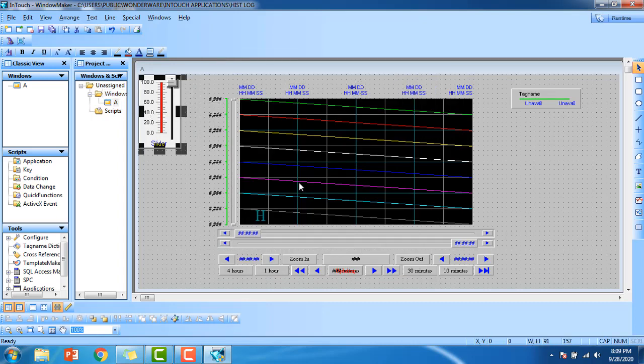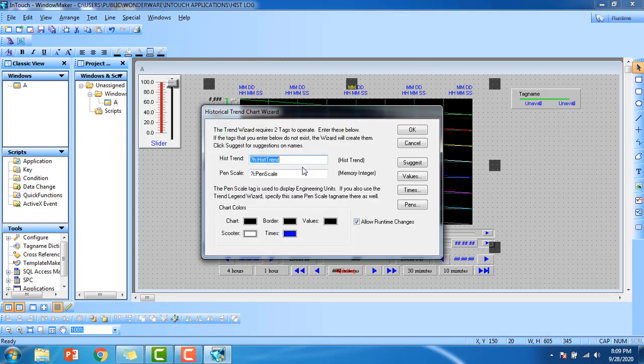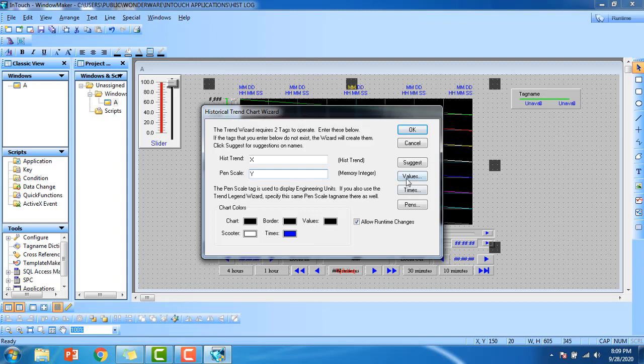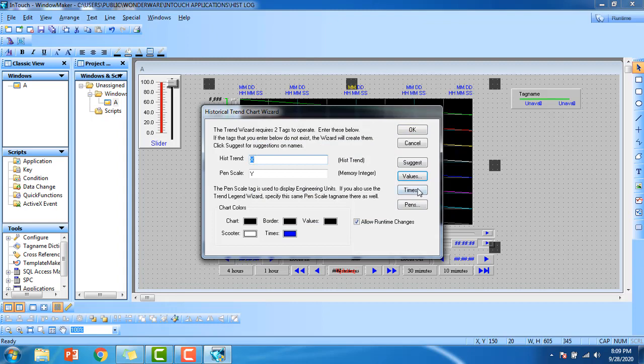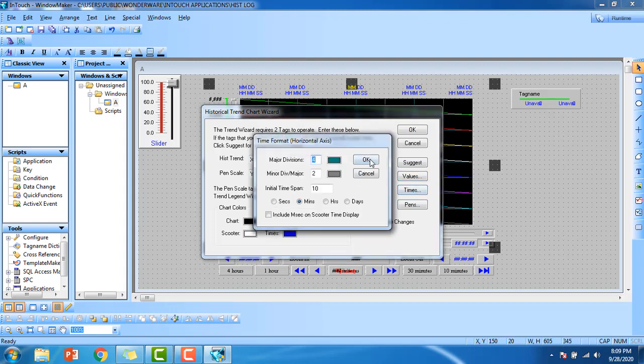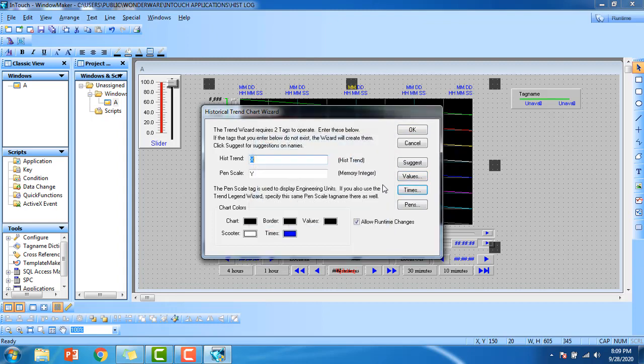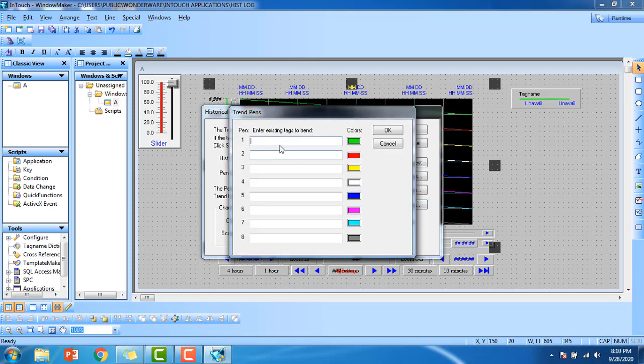Go to the trend, double click on it. I am going to give X and the pen scale as Y. You have to give the same historical trend time and pen scale for the zoom panel and the tag name pen. You can enter the pen as the slider name. My color will be green. They can have eight different pens so I can give eight different inputs and log inputs. Click OK.